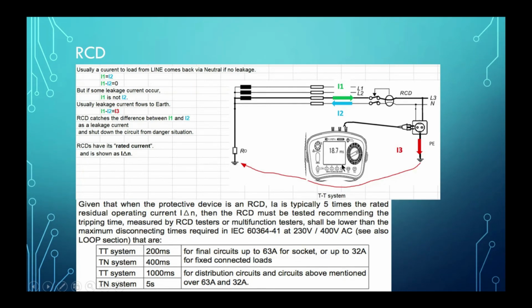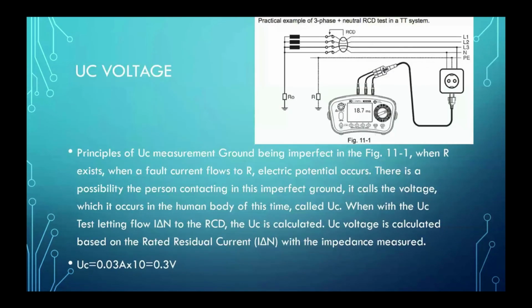Okay, how many seconds? Okay, and tripping current. Whether this tripping current is still under the safety value, safety range. So these are two of the tests for which we use our instrument. Okay, understand? Okay, we go to this UC voltage.